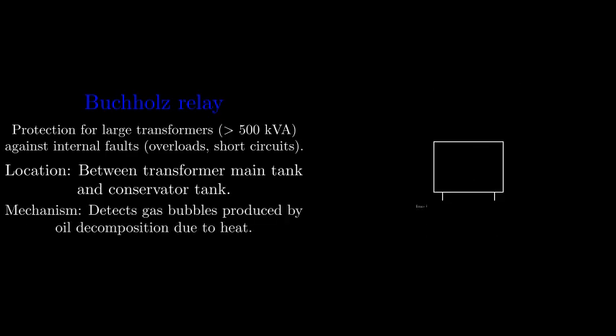Let's consider an overload. An overload causes the oil to overheat and decompose, producing gas bubbles. These bubbles travel up to the relay. In the relay, these bubbles accumulate in the chamber and displace oil. The rising oil level lifts a float, which activates a mercury switch. This switch closes an alarm circuit, warning operators of a potential problem.